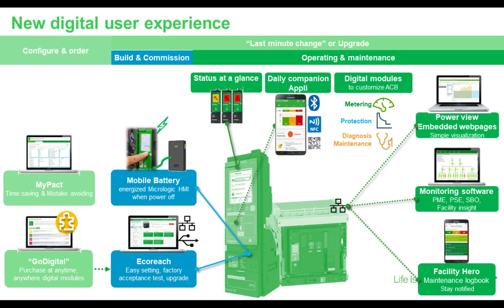Let's look at the new digital user experience. New breakers bring more data to users' fingertips. We can now configure breakers with a lot more options and make it easier for upgrading or even in new equipment. We can build in communication, mobile batteries to operate the trip units, EcoReach, which can add software and communications to the breaker. We can also do operating and maintenance. Using Bluetooth, we can monitor the trip units and monitor the condition of the breaker. Those are some added features now that weren't in older model breakers with older trip units that just covered the basics of tripping.